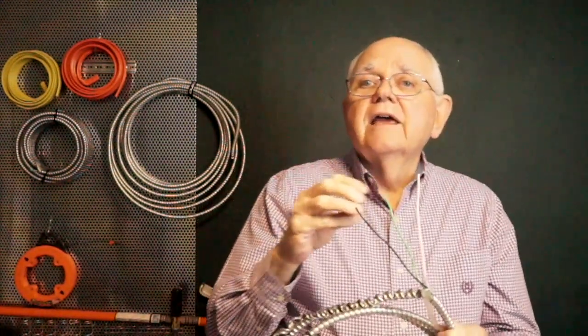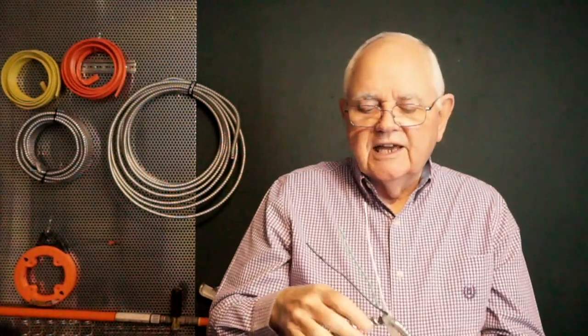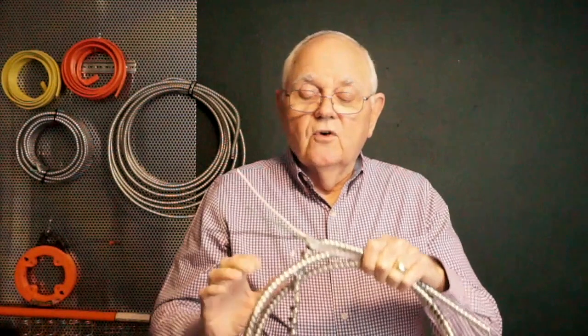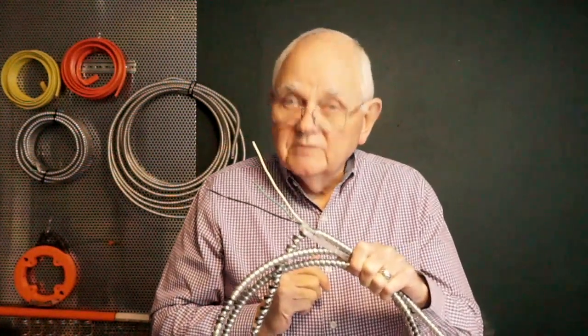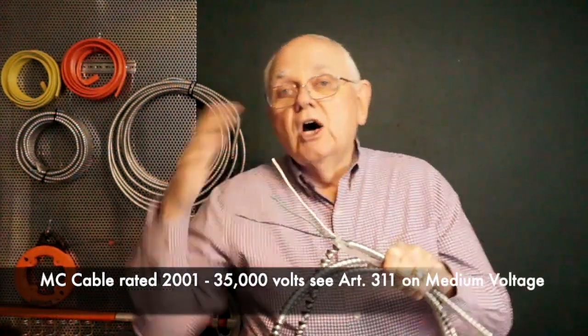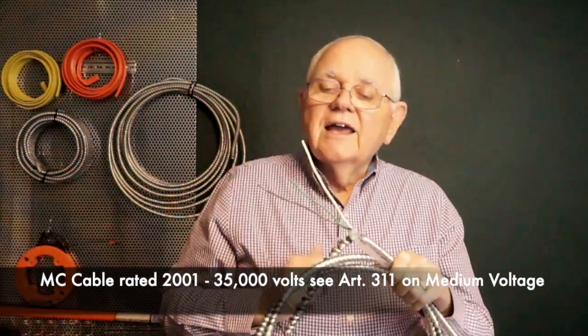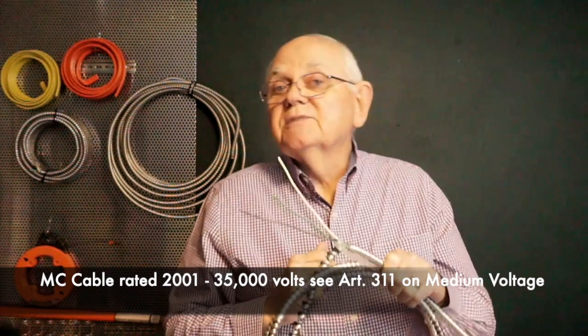I can get it with optical fiber cable. I can get it with both power and control cables on the inside of it, where they'll each be separated by the binder, each type of cable. So I do get proper separation inside the MC cable. I can buy it with just one conductor if I want to. I can buy it with insulation rated all the way up to 35,000 volts. Now, the MC cable itself is covered in Article 330. If my insulation on my MC cable is rated from 2001 on up to 35,000 volts, then I have to go to Article 311, which addresses medium voltage cable.